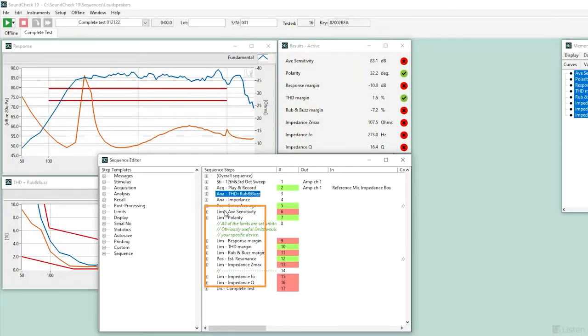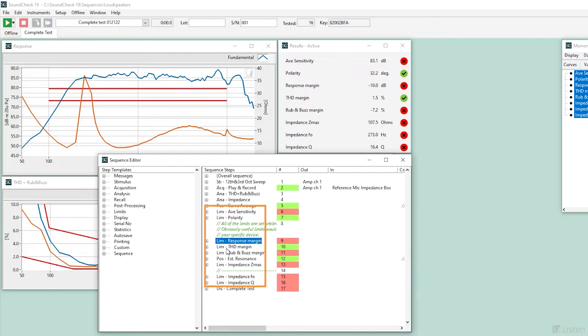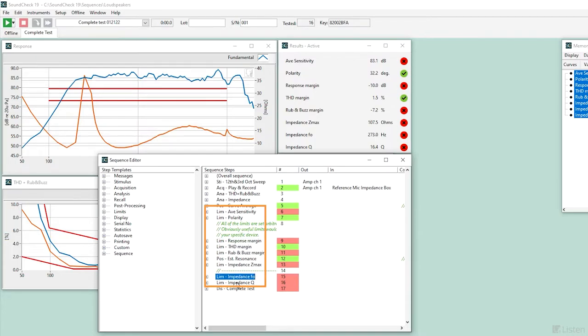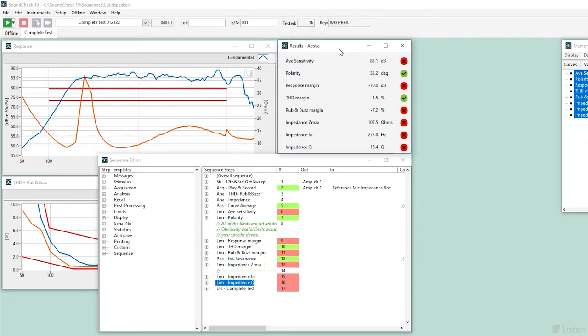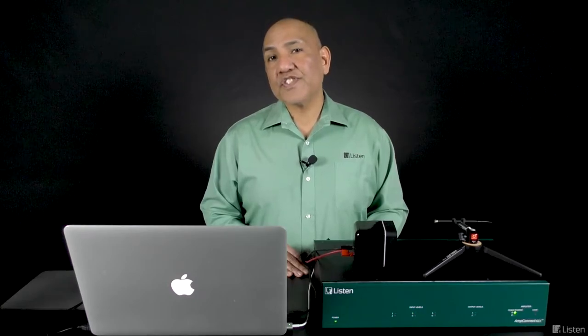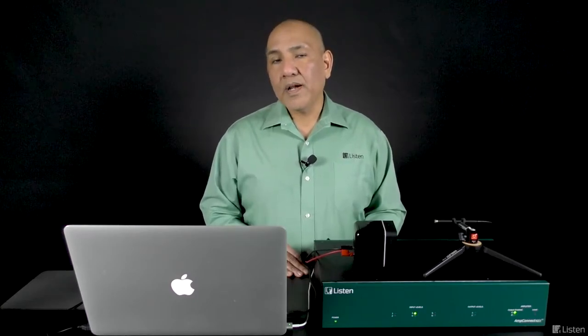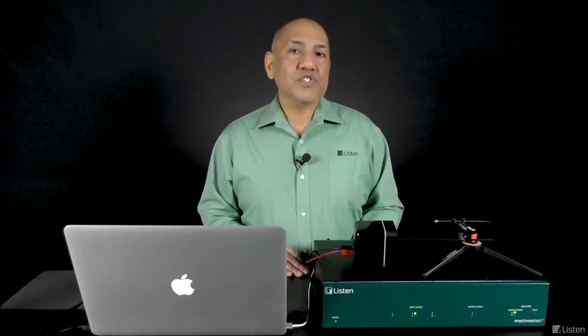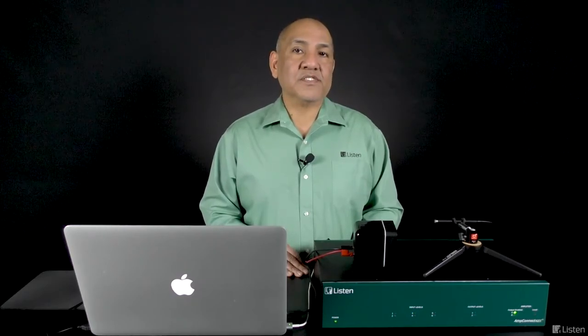Let's look at pass and fail limits. Limits are essential for qualifying your device on a production line. Setting limits in SoundCheck is fast and easy. The sequence has some default arbitrary limits. Many of them have failed because I didn't specifically set the pass-fail limits to conform to this particular device under test. There are two common methods for setting limits. One, measure a golden reference unit and build acceptable plus-minus tolerances from the reference unit. Or two, measure a large sample and use SoundCheck statistics.